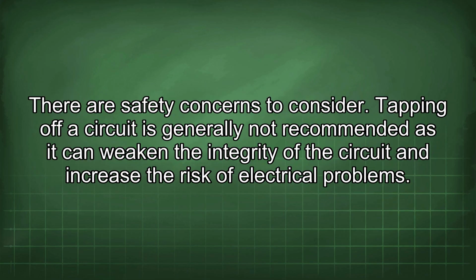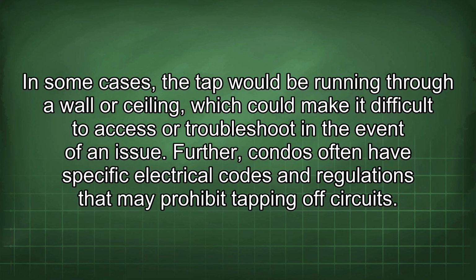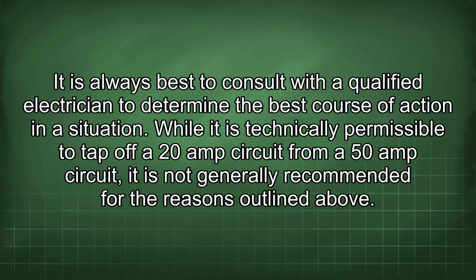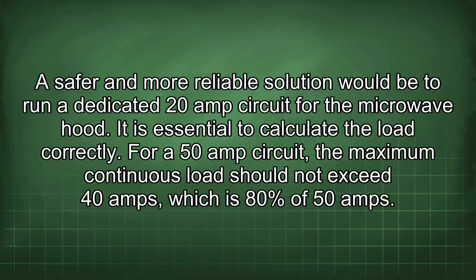There are safety concerns to consider. Tapping off a circuit is generally not recommended as it can weaken the integrity of the circuit and increase the risk of electrical problems. In some cases, the tap would be running through a wall or ceiling, which could make it difficult to access or troubleshoot in the event of an issue. Further, condos often have specific electrical codes and regulations that may prohibit tapping off circuits. It is always best to consult with a qualified electrician to determine the best course of action in a situation. While it is technically permissible to tap off a 20 amp circuit from a 50 amp circuit, it is not generally recommended for the reasons outlined above. A safer and more reliable solution would be to run a dedicated 20 amp circuit for the microwave hood.